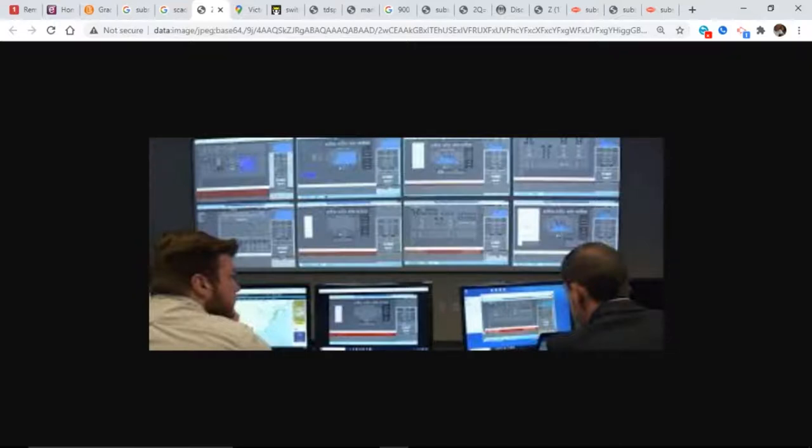They're also able to, and you remember in the description, what else can they do other than monitor? Supervisory. Control. Control, all right? So they can open or close breakers or switches in a substation if they're SCADA capable, if it's a switch that has a control to do that.